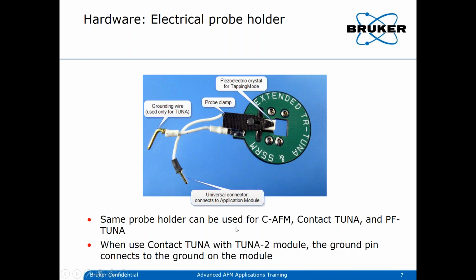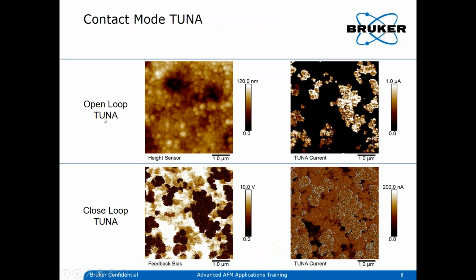Again, this holder can be used for conductive AFM, contact TUNA, or PeakForce TUNA. And when you're using it for contact TUNA measurements with the TUNA 2 module, then the ground pin connects to the ground on the module. Again, not for PeakForce TUNA.